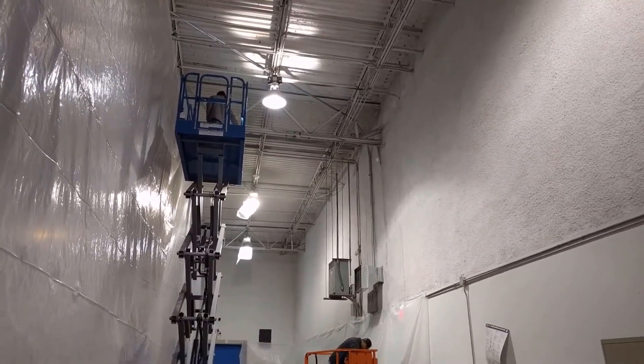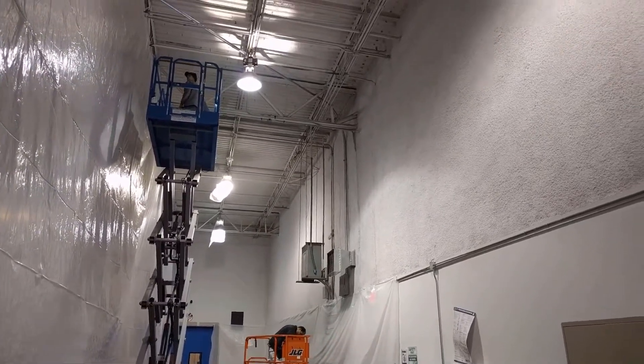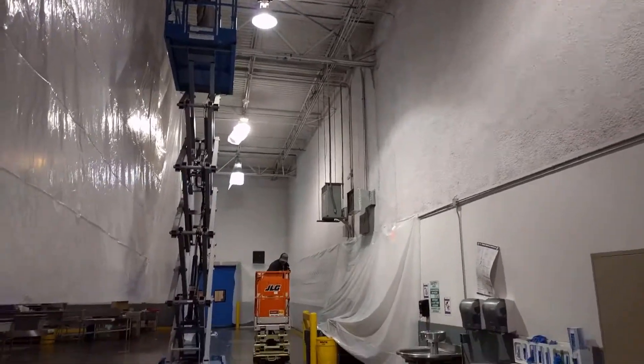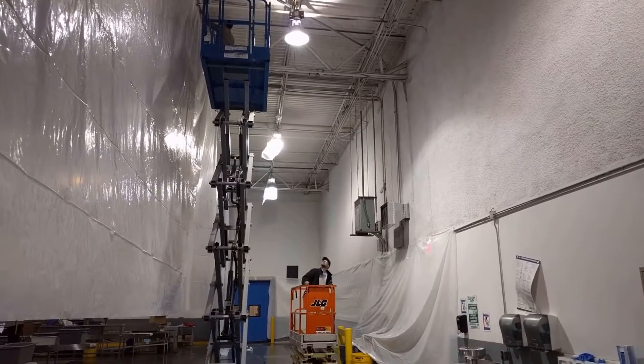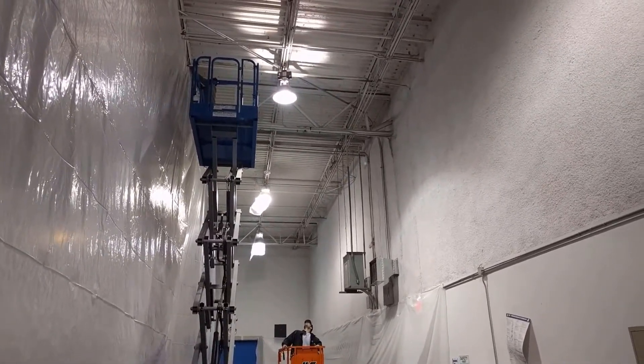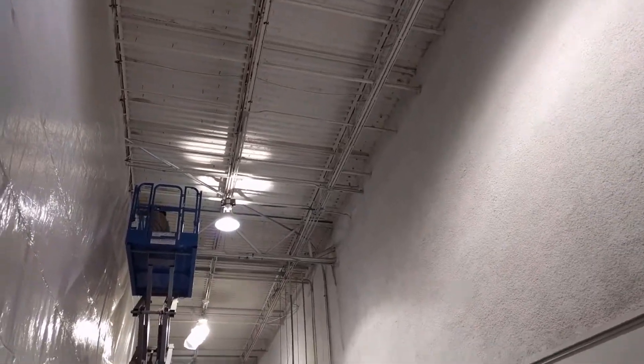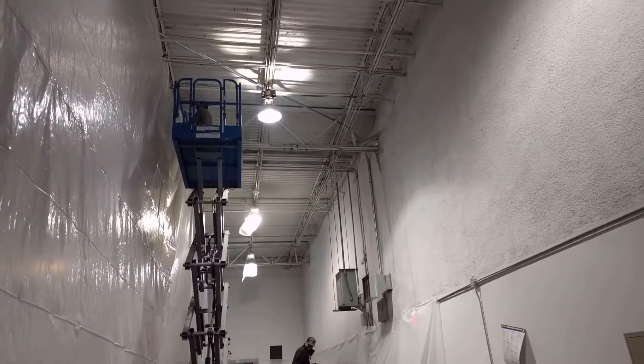We're at a food packaging facility and we're going to spray the top of this wall with closed cell foam. The room to the right of us is heated and cooled — it's an office — so this area in here is 50 degrees. This is causing sweating along the top and resulting in rust. We're going to spray closed cell foam all along this wall and down this wall here as well.